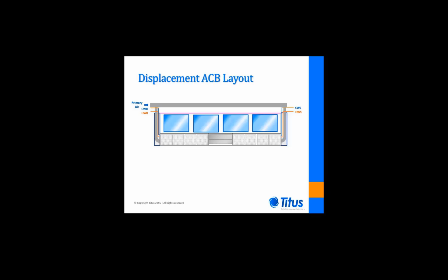The water supply for all of the ACB units can be provided through one chase and returned through the other. The individual ACB heat transfer coils are fed in parallel, and the piping is run behind the units and against the wall. Primary air is supplied to multiple ACB units in series. A single duct connection should be limited to feeding no more than 3 units due to noise and pressure limitations. So often this involves air supply connections on both sides of the classroom.